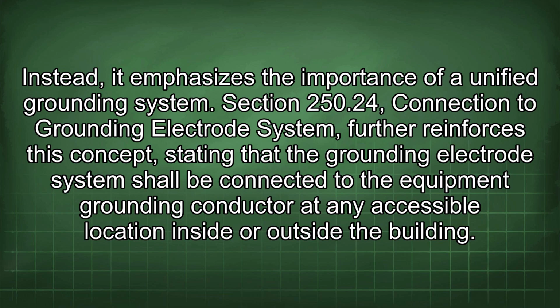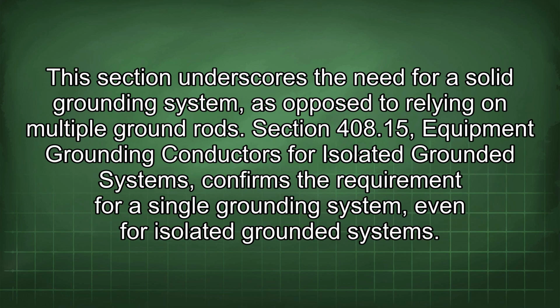Section 250.24, Connection to grounding electrode system, further reinforces this concept, stating that the grounding electrode system shall be connected to the equipment grounding conductor at any accessible location inside or outside the building. This section underscores the need for a solid grounding system, as opposed to relying on multiple ground rods.